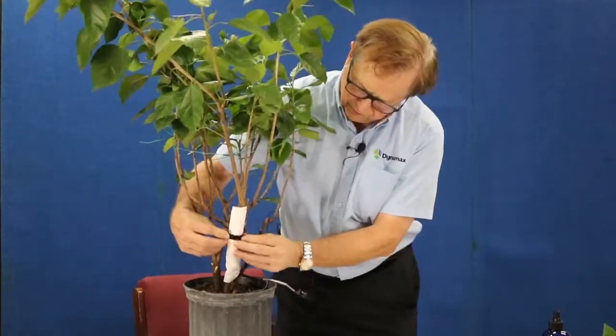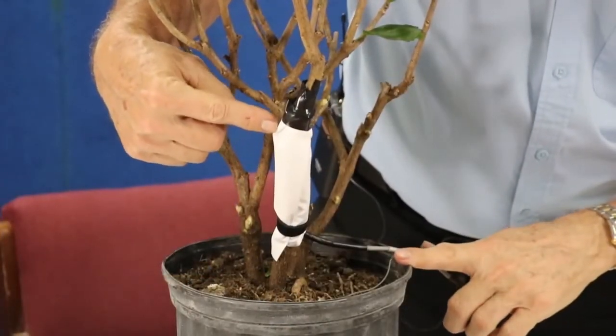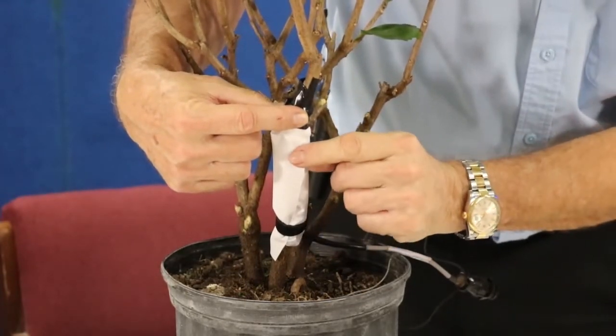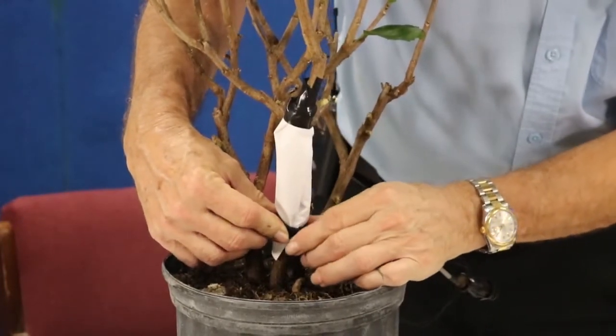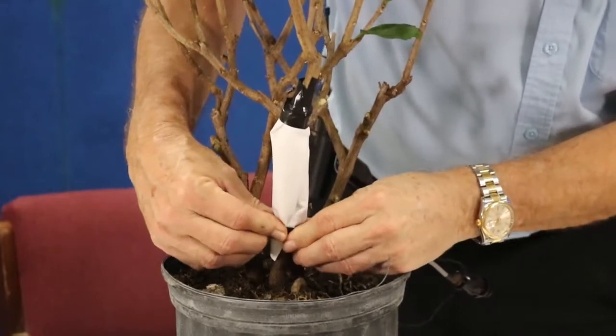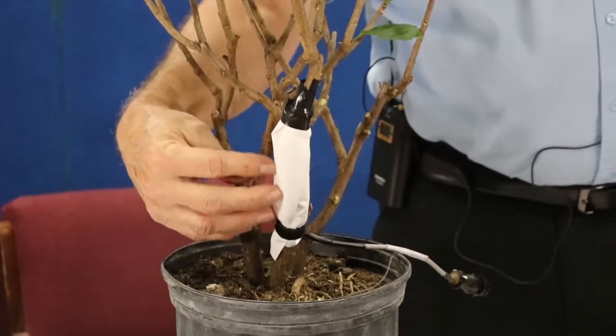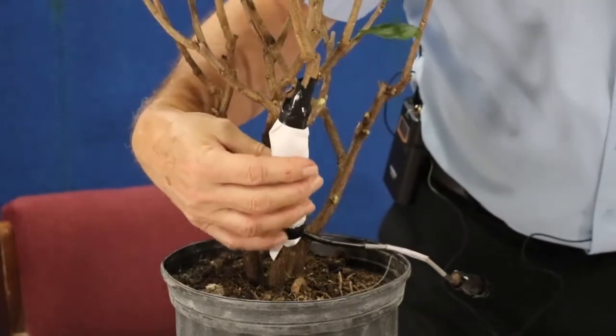Okay, that's double-sided Velcro, just holding it in place, and then I'll secure the top. This part of the installation, I have taped 2 wraps of flexible tape around the top, so I'm securing the Gore-Tex raincoat over the Sap Flow sensor. The bottom, I'm just using one of the double-sided Velcro, so it's allowing any liquid to drain out. But the main thing is that I want the water vapor to exude through this cloth, and the bottom is going to be open. So that's going to extract the water vapor, it's going to reduce condensation buildup inside, and then it'll reduce corrosion or any possible damage to the stem.